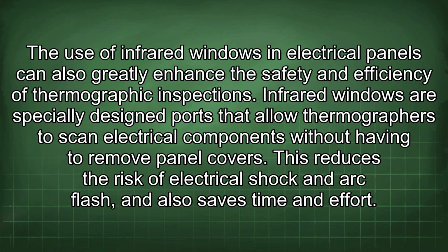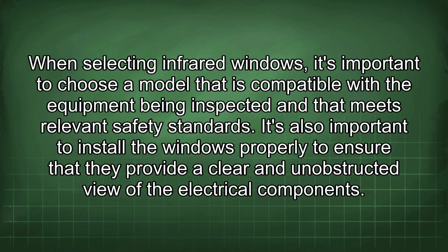The use of infrared windows in electrical panels can also greatly enhance the safety and efficiency of thermographic inspections. Infrared windows are specially designed ports that allow thermographers to scan electrical components without having to remove panel covers. This reduces the risk of electrical shock and arc flash, and also saves time and effort. When selecting infrared windows, it's important to choose a model that is compatible with the equipment being inspected and that meets relevant safety standards. It's also important to install the windows properly to ensure that they provide a clear and unobstructed view of the electrical components.